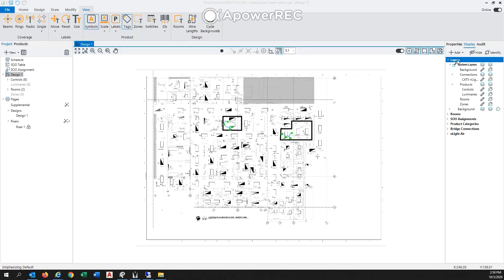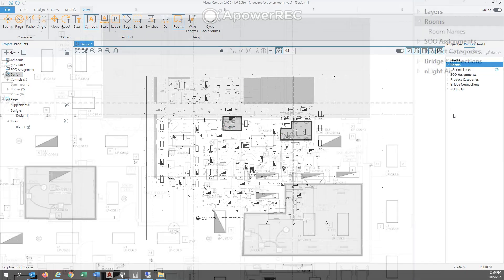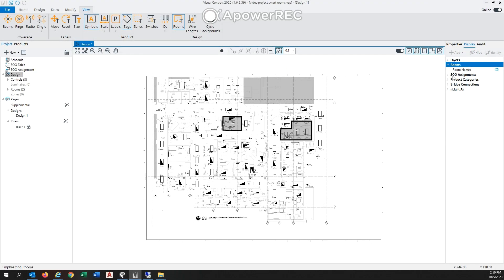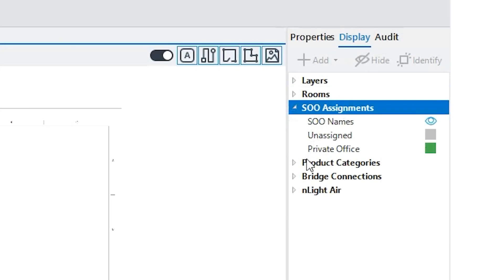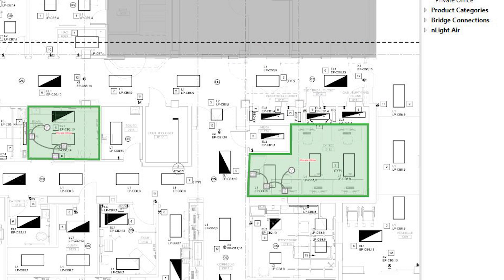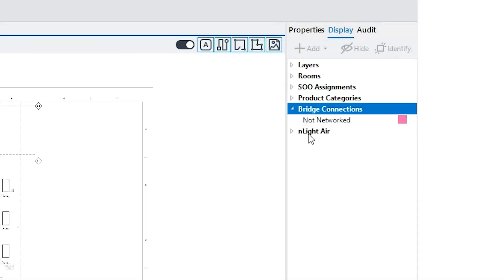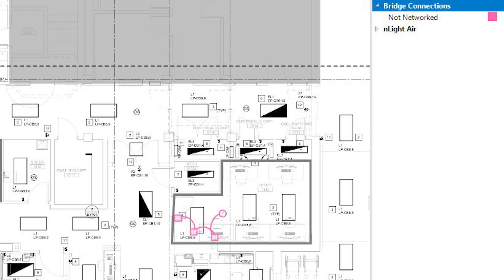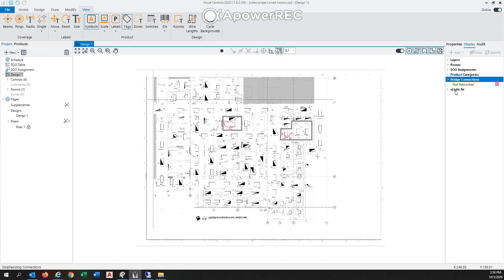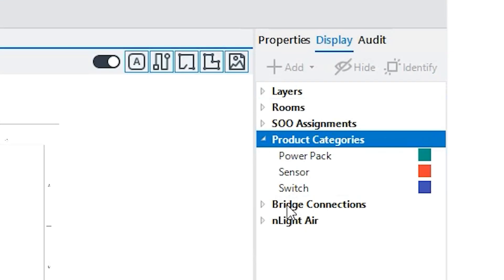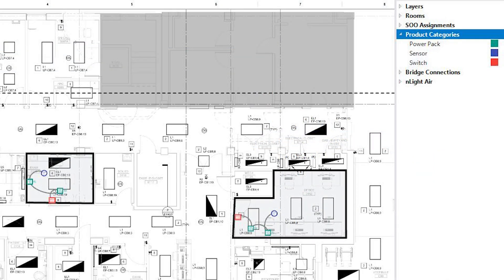There are five display modes to help you analyze the different aspects of your project. Layer view displays the objects based on the layer settings. Room view displays rooms as shaded so you can quickly find missing rooms. Sequence of operation assignment view displays a color-coded SOO assignment for each room assigned to a sequence of operations. Bridge connection view displays products color-coded by their associated bridge connection. And product category view displays products of the same type in the same color.